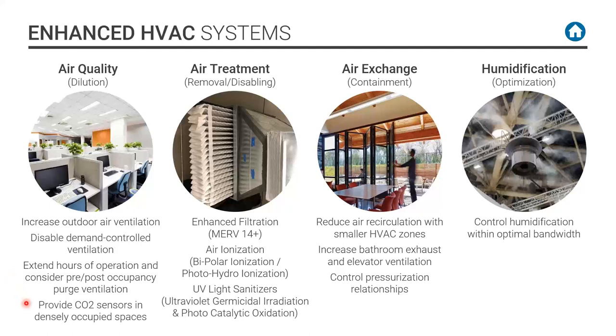And in very small spaces, like conference rooms, et cetera, especially in a new project, we're asking to put CO2 sensors in, which, as they detect CO2 levels going up, will bring in more outside air in the system. So now we've diluted the contaminants. The next thing is we want to remove it.